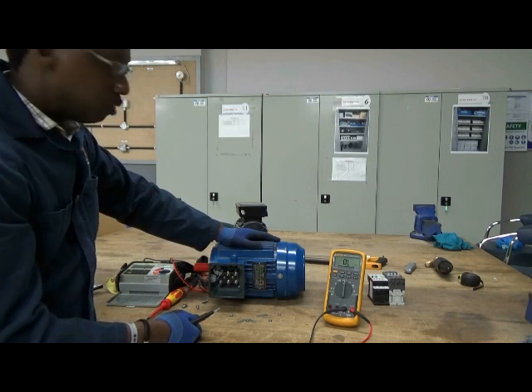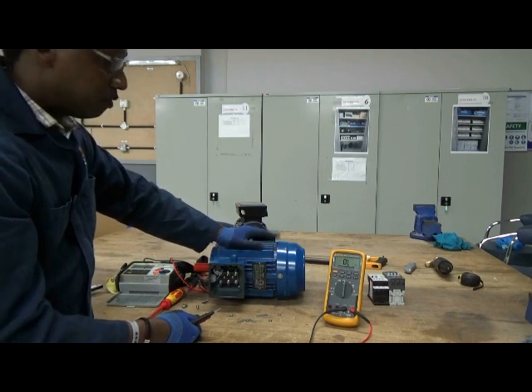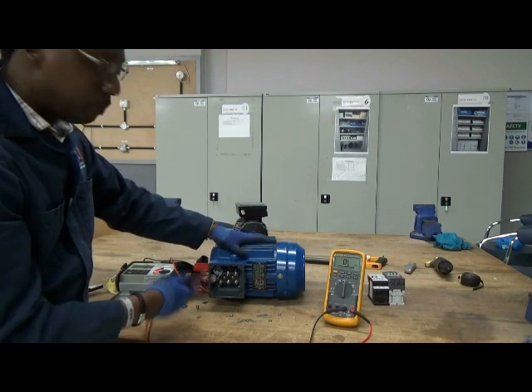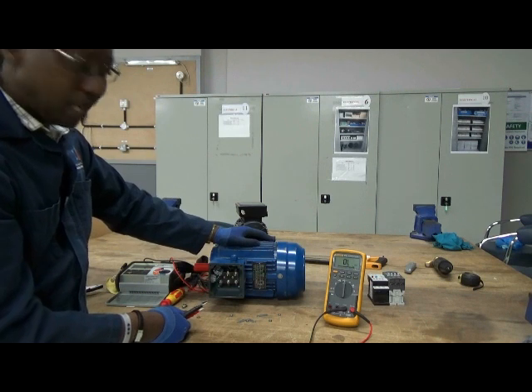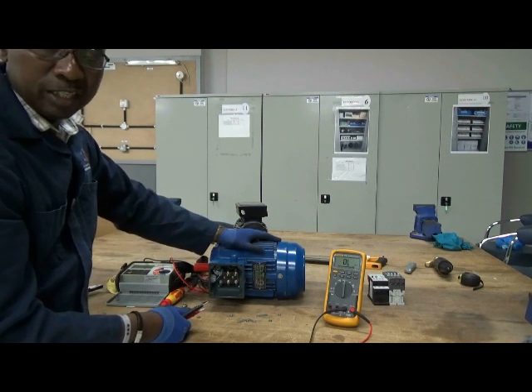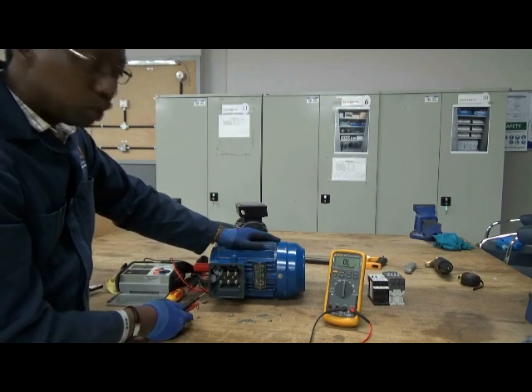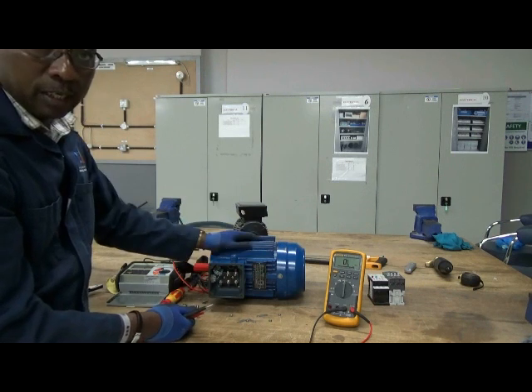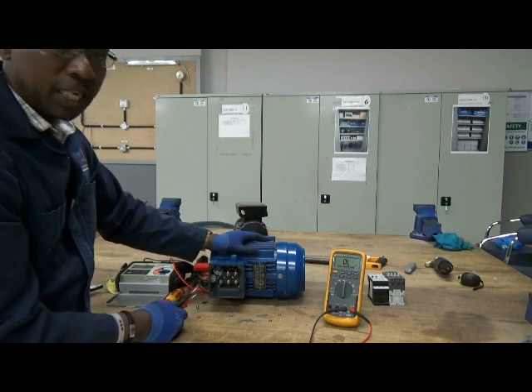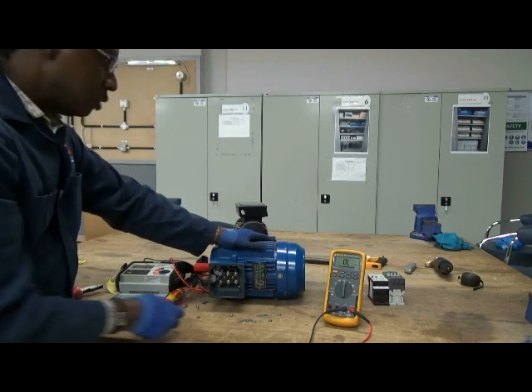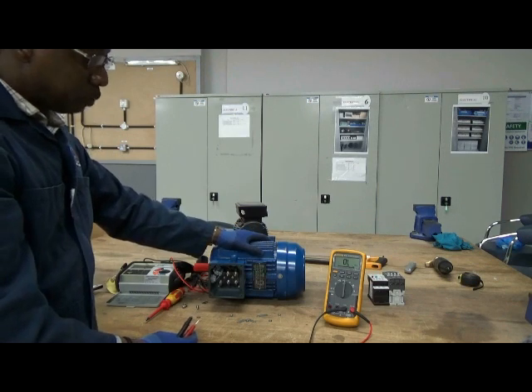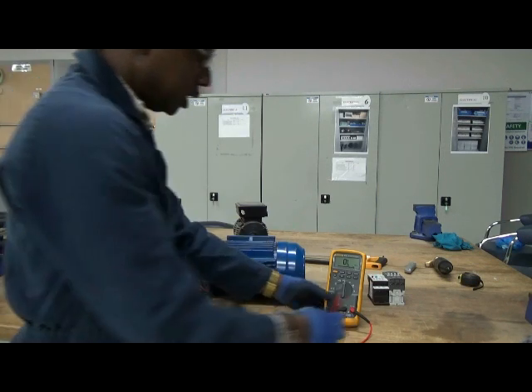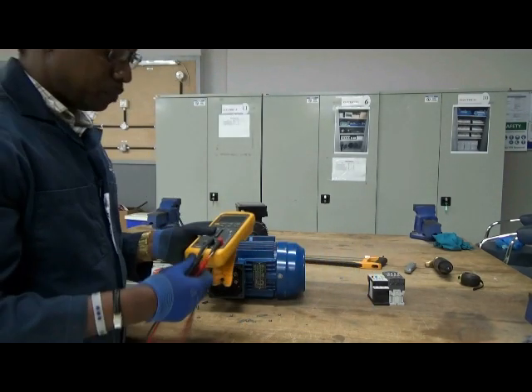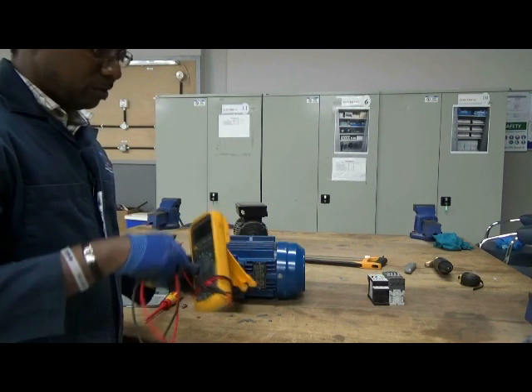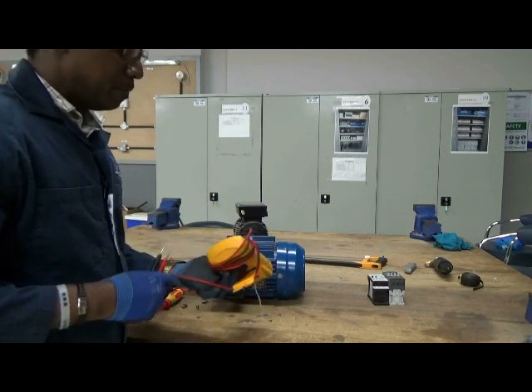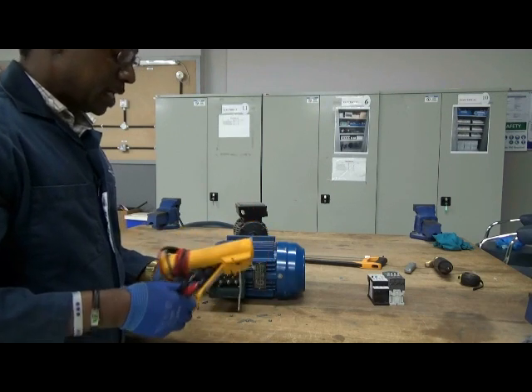And if that is the case, then we would not be able to connect this motor to the supply. Because if one of the windings is touching the body of the machine, it means if I put on the supply, the body of the machine becomes live, because this is metal. So any metal is a conductor of electricity. So the windings must be insulated from the body of the machine and from each other. For us to determine that, we need to carry out what we call an insulation resistance test. And that's a very special test where we need a special instrument called an insulation resistance tester, popularly known as the Megger.